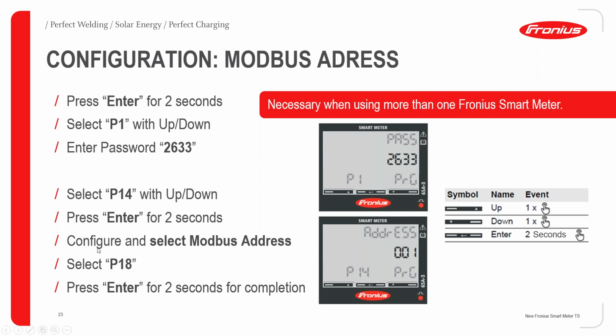Yeah, and then you can configure or select the Modbus address. You can choose if it is 1 or 2, it's up to you. Then as soon as you press enter, it will save. Then you have to go to the P18, then press enter for 2 seconds to complete this setup and then go out.